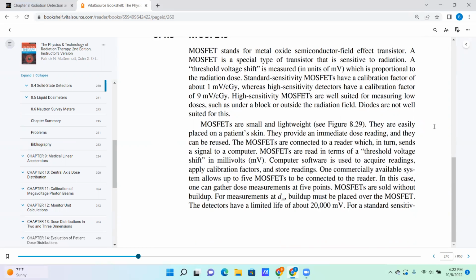MOSFETs are small and lightweight. They're usually placed on a patient's skin. They provide an immediate dose reading and can be reused. The MOSFETs are connected to a reader, which in turn sends a signal to a computer. MOSFETs are read in terms of threshold voltage shift in millivolts. Computer software is used to acquire the readings, apply calibration factors, and store readings. One commercially available system allows up to 5 MOSFETs to be connected to the reader. In this case, one can gather dose measurements at 5 points.